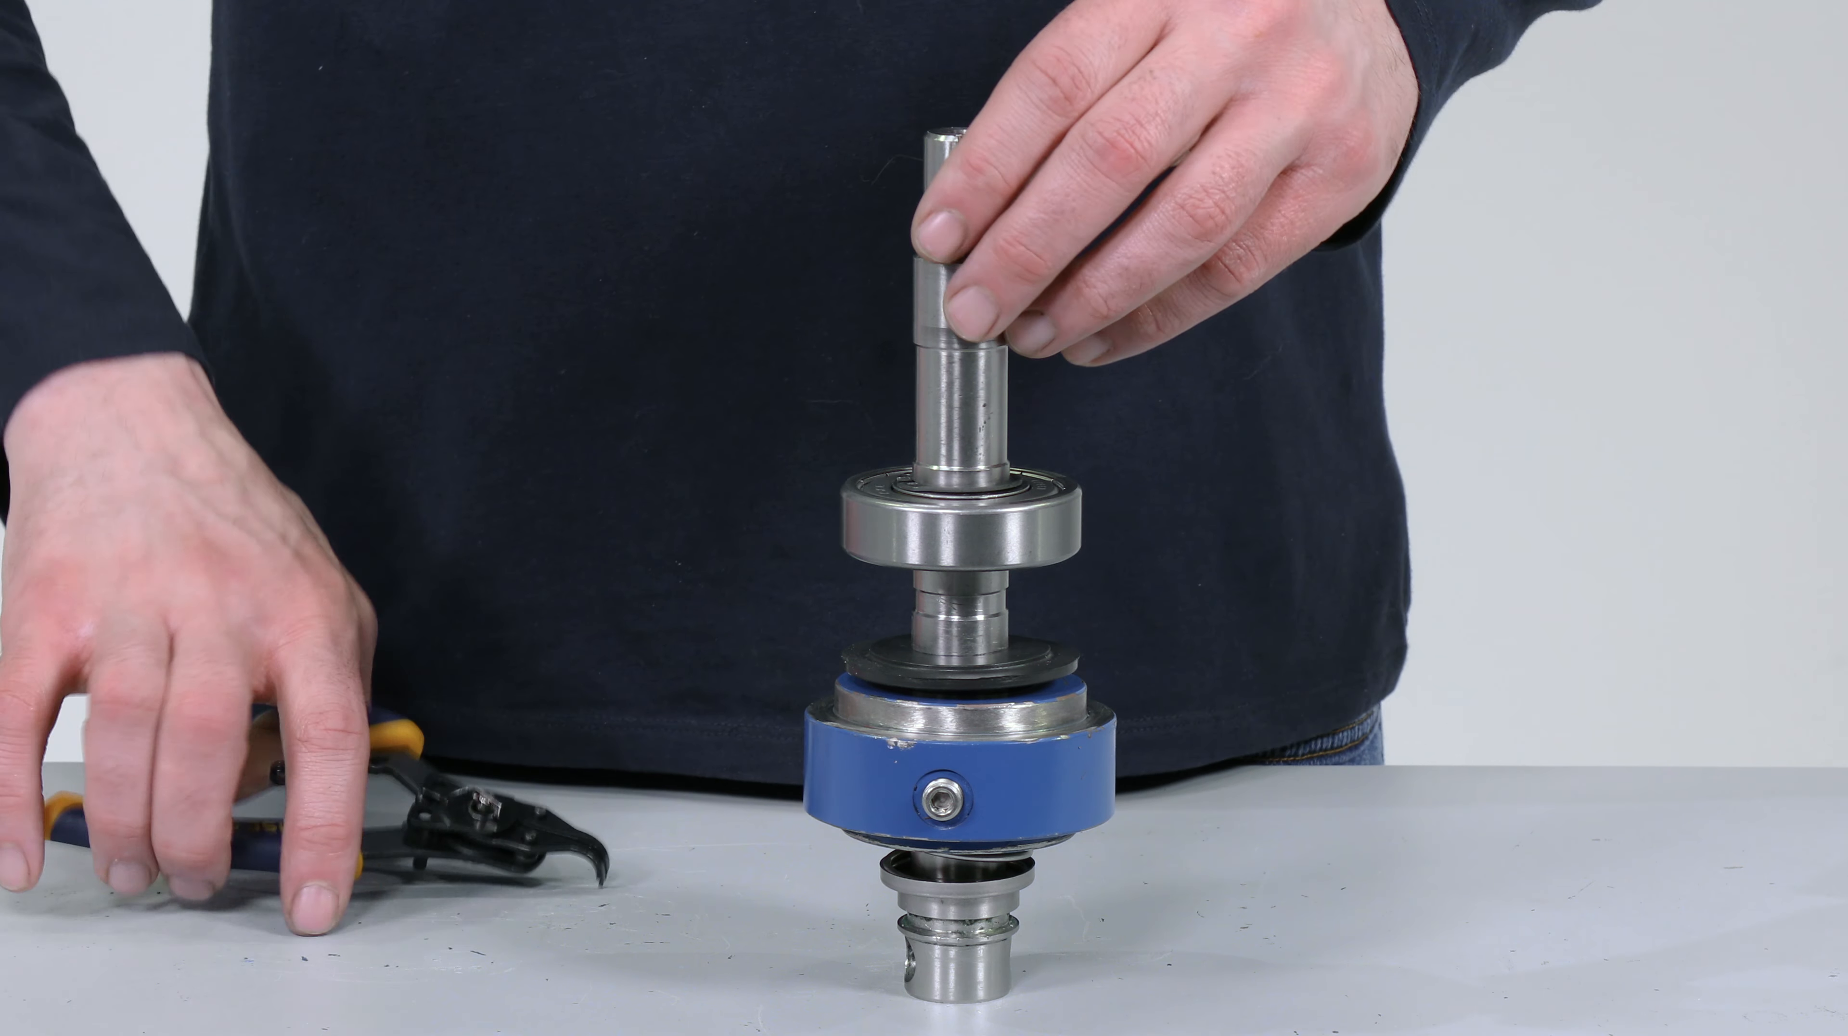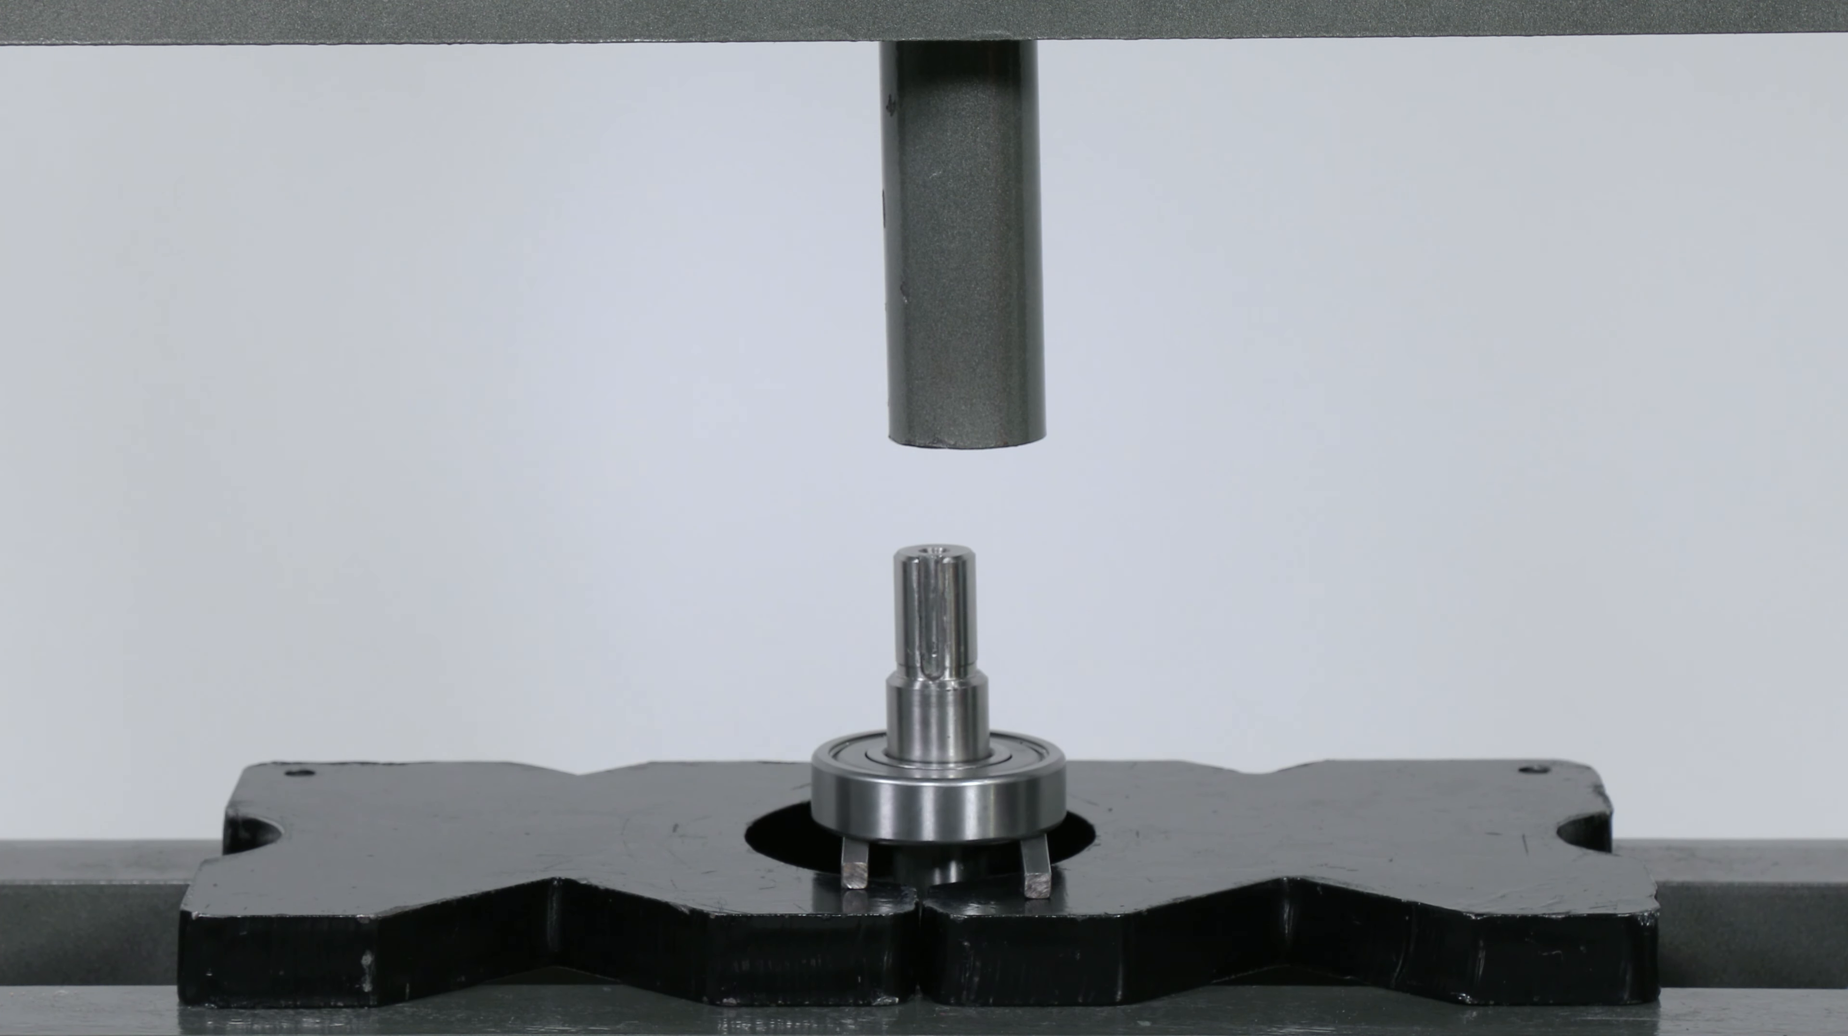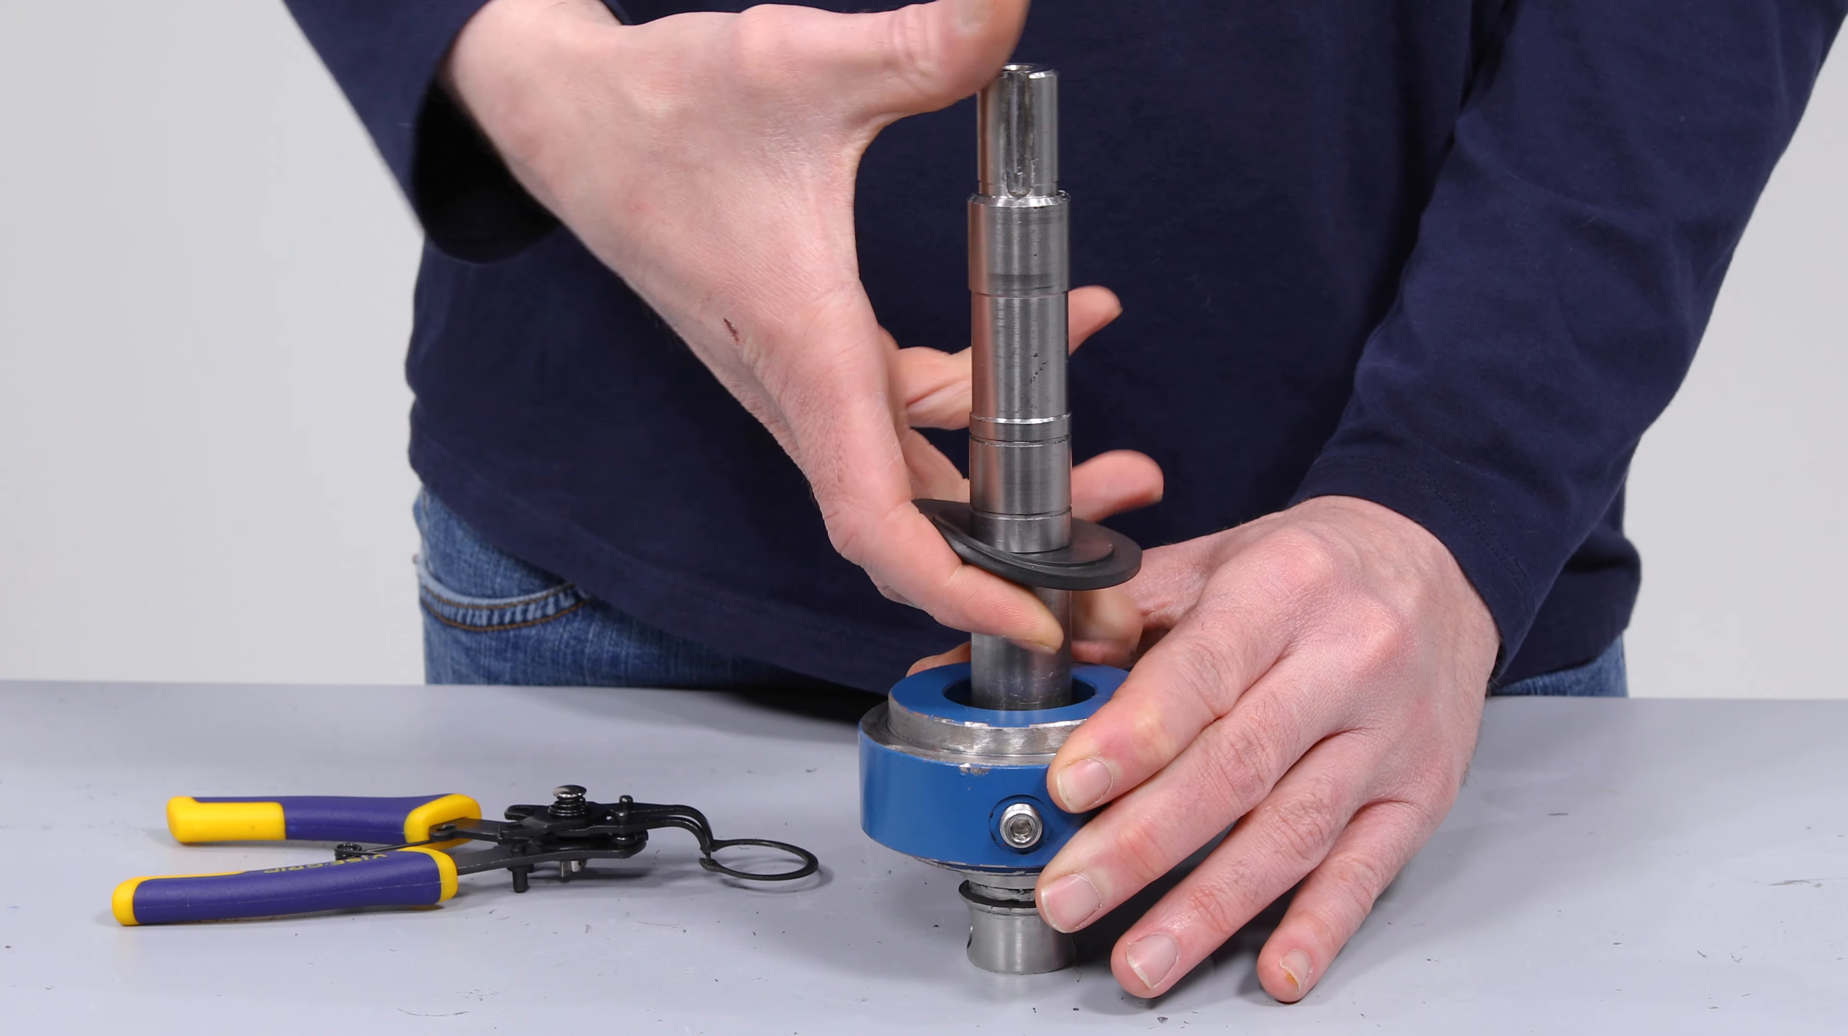Put the drive shaft on the workbench and remove the first snap ring. Place the drive shaft in a press and remove the second bearing. Place the drive shaft back on the workbench and remove the last snap ring with small snap ring pliers. Slide the flinger ring off of the drive shaft.